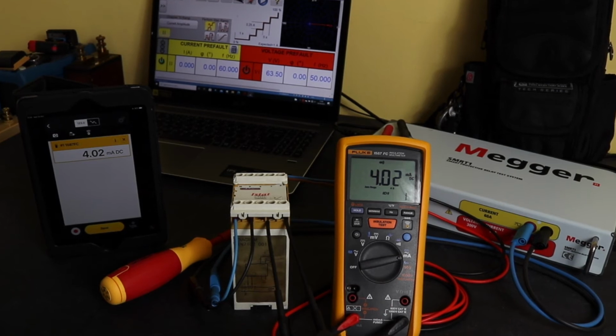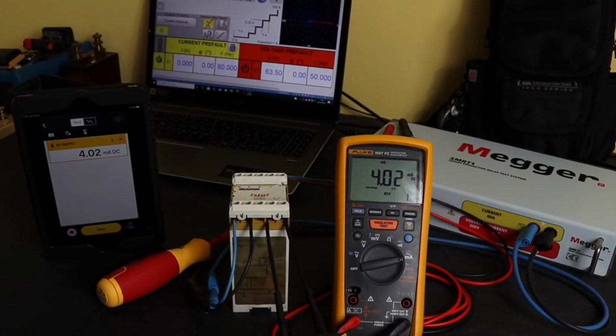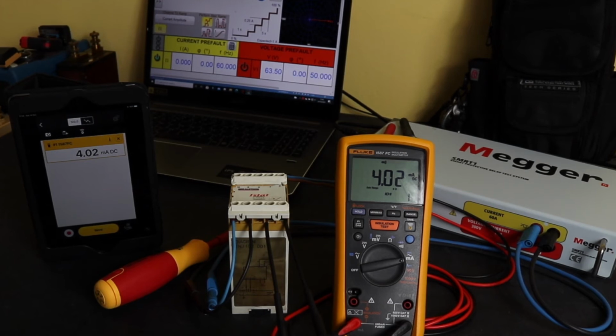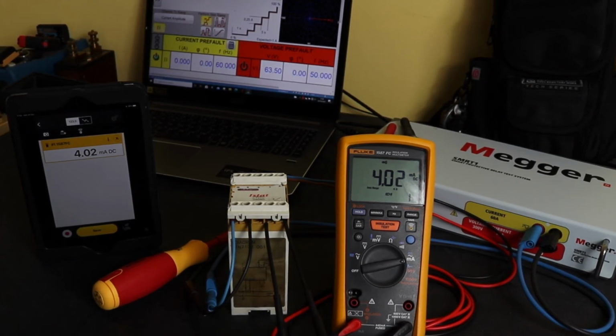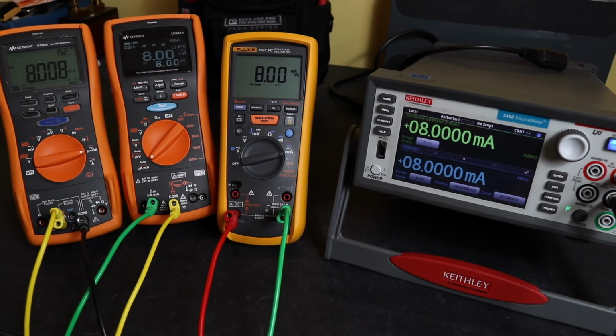So technically I can't really be using this setup to take these measurements, but there are a couple of caveats that enable me to actually make these measurements. So the first reason why I can get away with having such a low accuracy on the Fluke is that the transducers that I'm measuring are purely for indication into the control system. I'm not doing any fiscal metering or any weights and measurements systems. It's purely for trending of the current in motors and distribution boards and systems like that. So absolute accuracy is not paramount for that application.